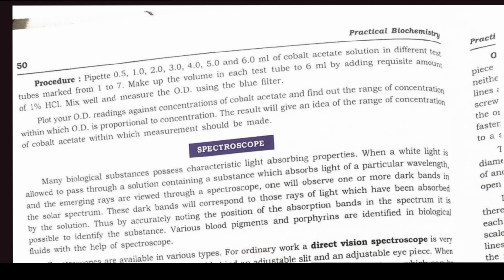Plot your OD reading against concentration of cobalt acetate and find out the range of concentration within which OD is proportional to concentration. The result will give an idea of the range of concentration of cobalt acetate within which measurement should be made.